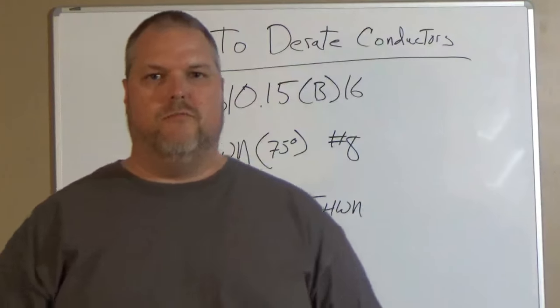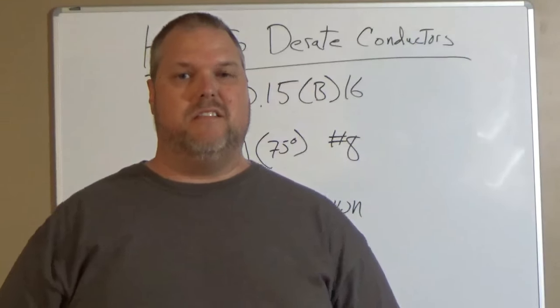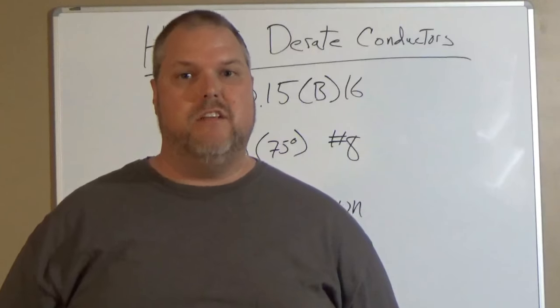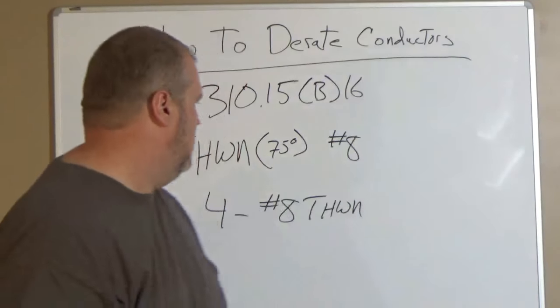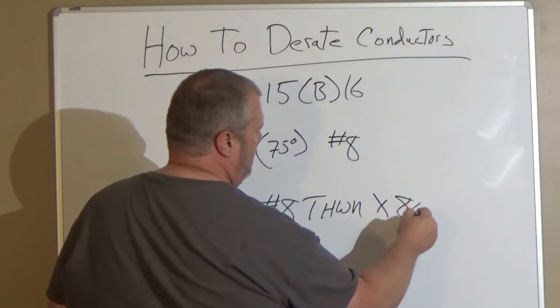I look into 310.15.B.3.A, I look for four. I'm going to see four to six. That's going to tell me that I have to derate up to 80 percent. So I'm going to multiply this by 80 percent.